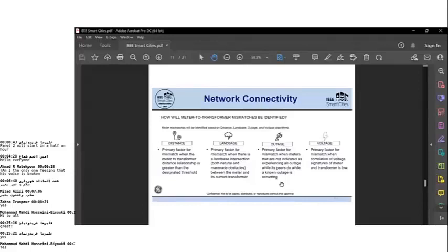So if such an infeasible geofeature is present in the database, that meter is likely mismatched. So it will look into the number of interactions of the meter-transformer pairs with those infeasible geospatial features, and will flag them as a mismatch. And for obvious reasons, this one cannot recommend a transformer because it's just using the geofeatures.